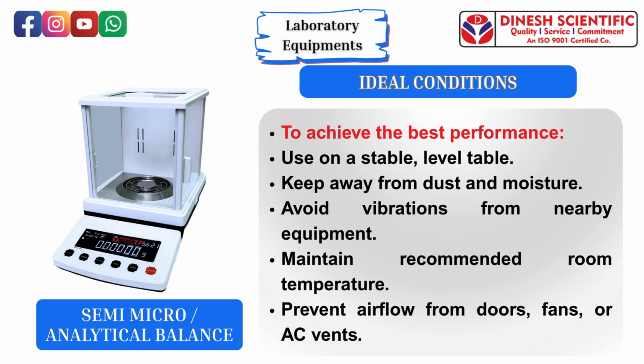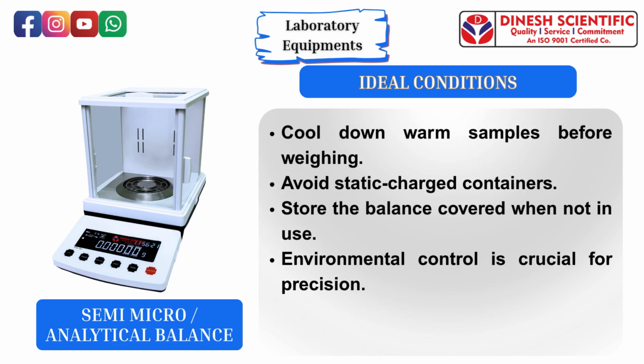Ideal conditions. To achieve the best performance, use on a stable, level table. Keep away from dust and moisture. Avoid vibrations from nearby equipment. Maintain recommended room temperature. Prevent airflow from doors, fans, or AC vents. Cool down warm samples before weighing. Avoid static charged containers. Store the balance covered when not in use. Environmental control is crucial for precision.